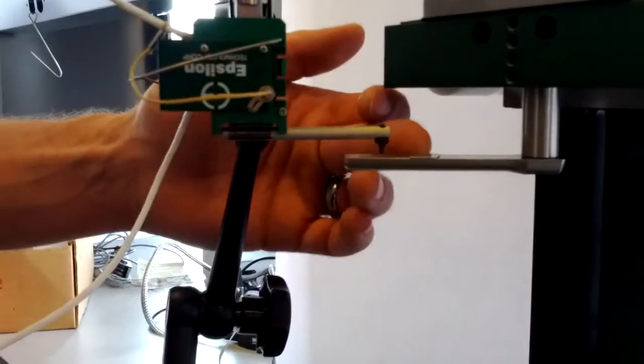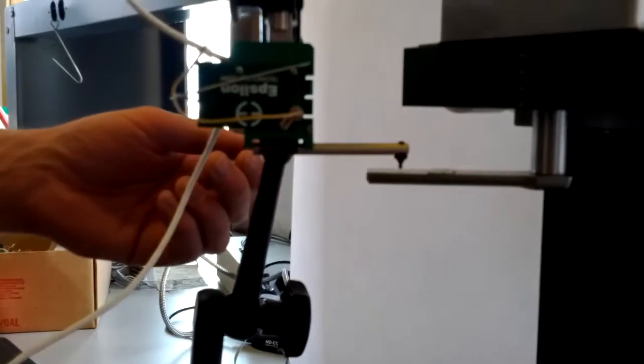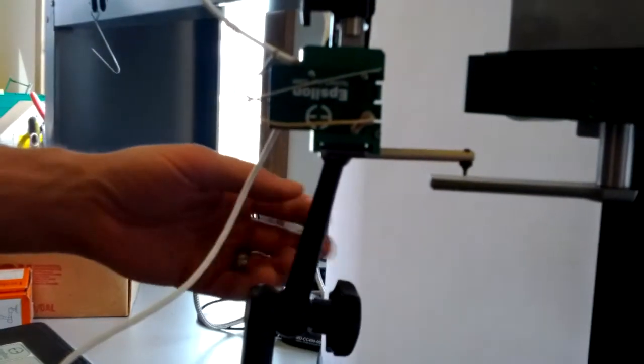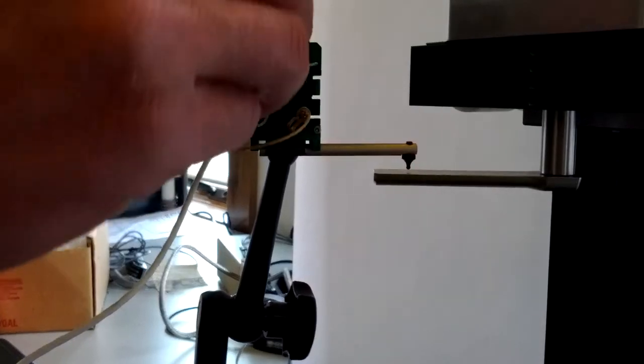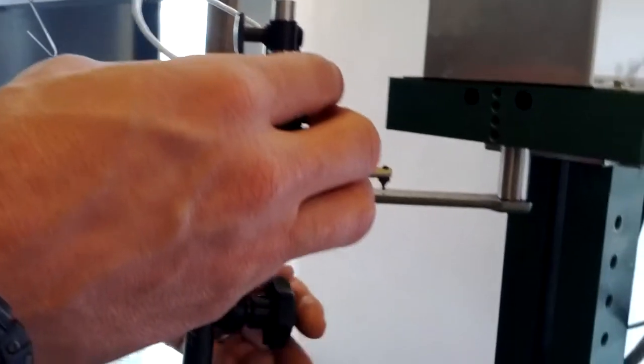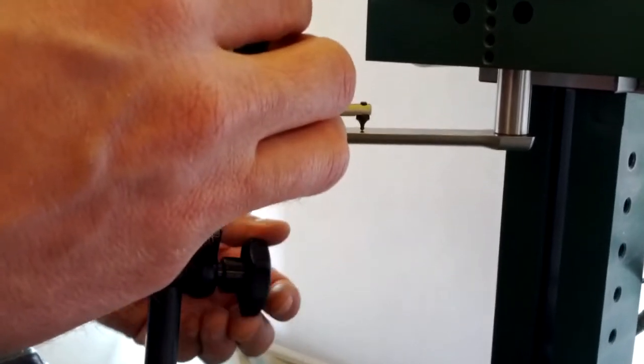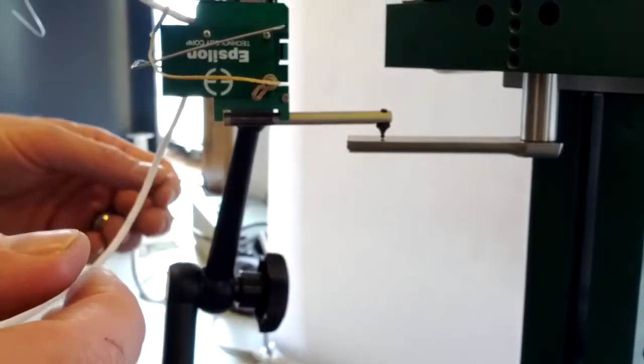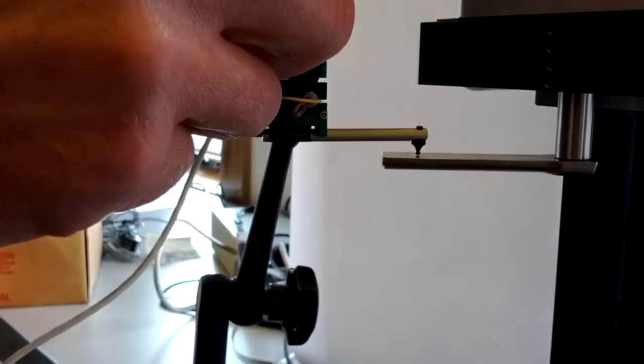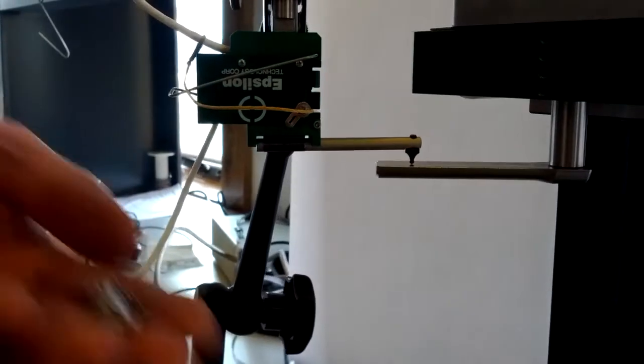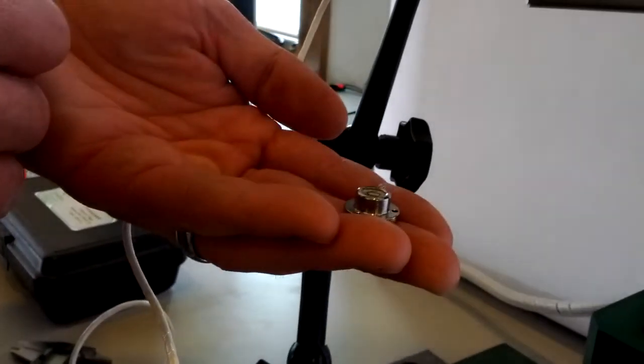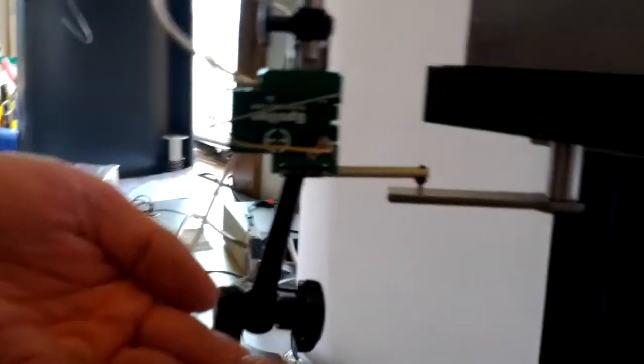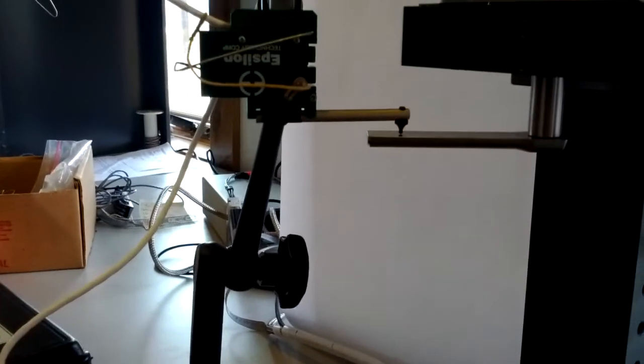An alternative approach, instead of using the gauge block, I can use my calibration stand to set this up. So in this case, again, I'll toss this level on here, and now I'm just going to bring it down to touch. And if you're off by a hair or it moves a couple of millivolts, it's really not a big deal. I did evaluate how close I need to be on the level, and basically I could do it reasonably well by eye if I paid attention after the fact. And we'll pull the pin.